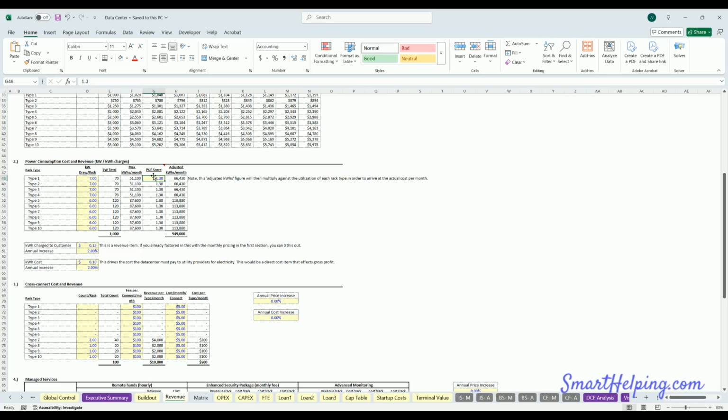You've got a PUE score, which is saying, well, if you're just using this many watts for just the IT equipment alone, and you have a PUE score of 1.3, that means you're also using electricity for the lights, for cooling, for other things. In the industry of data centers, this is measured in a ratio, and you can multiply by that to get the actual expected electricity spend.